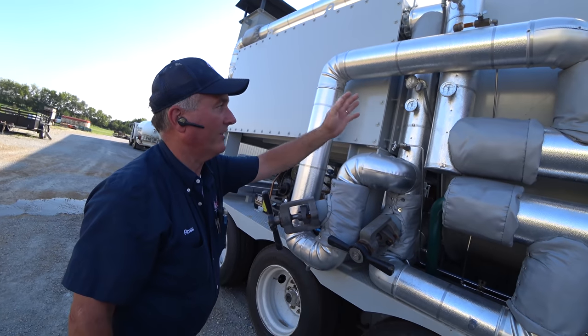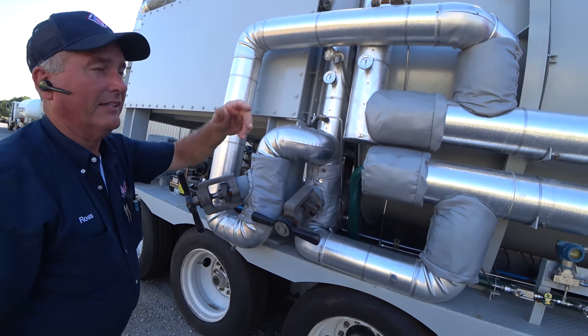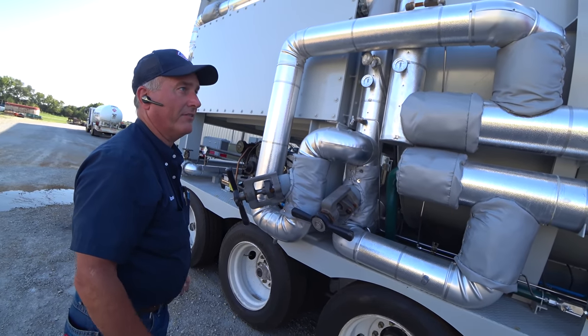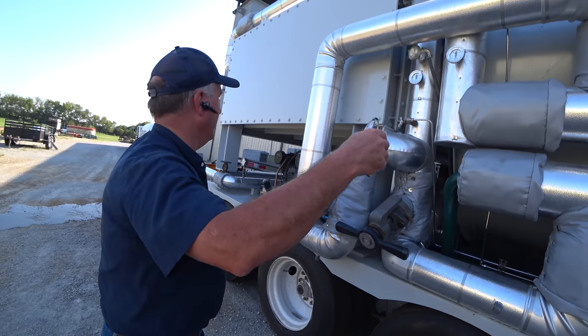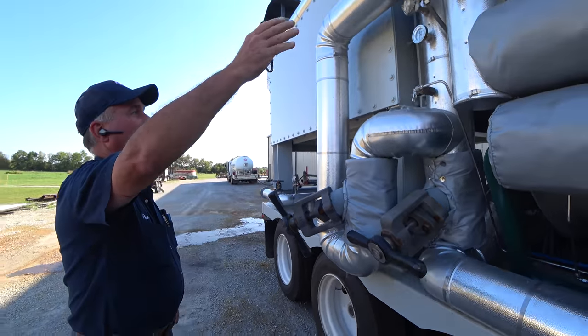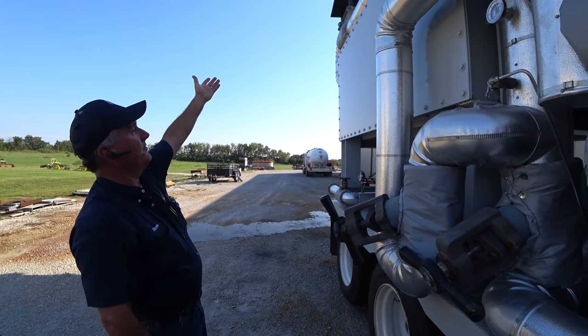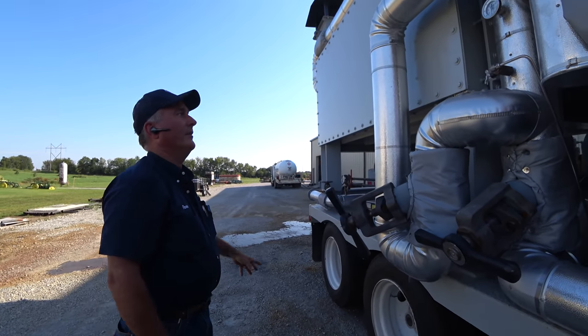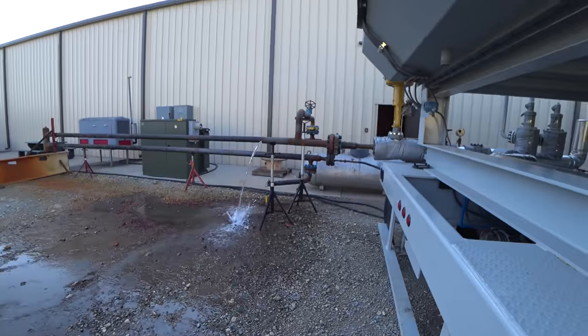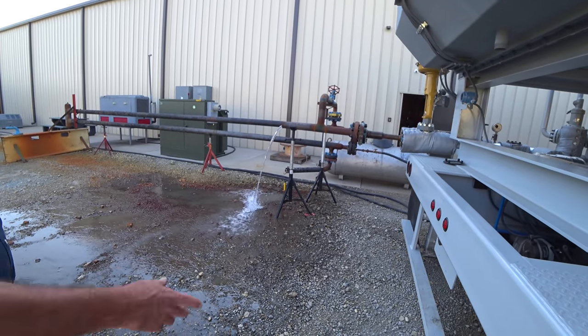that condenses the exhaust gases, which are combusting inside this big drum at about 1800 to 2200 degrees based on certain conditions. Anyways, those combustion gases flow over this coil, and it changes it from 1800 degrees and comes out up there at 200 or 300 degrees and absorbs a lot of heat in this coil. Here's my outbound water at the moment, and of course, that's just regular old drinking water right now. Yep. And so it's just a big steel pipe.